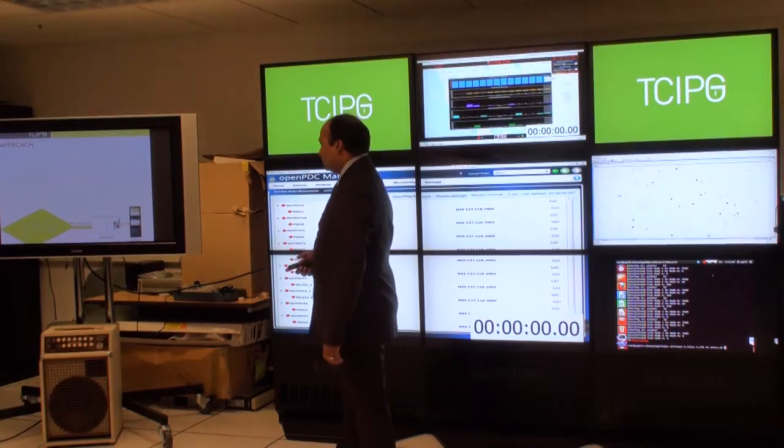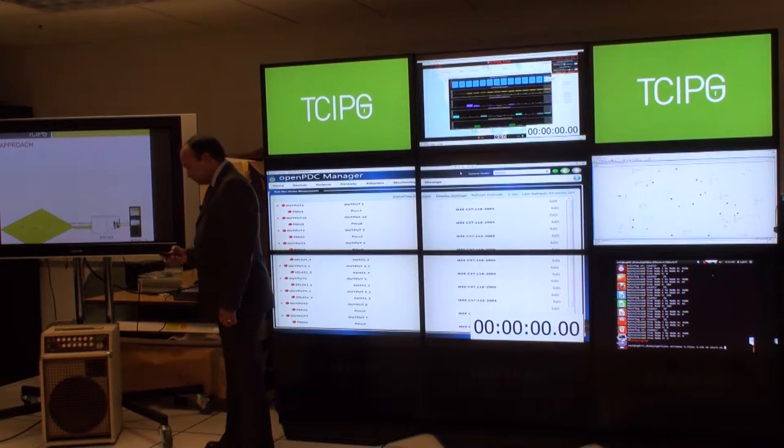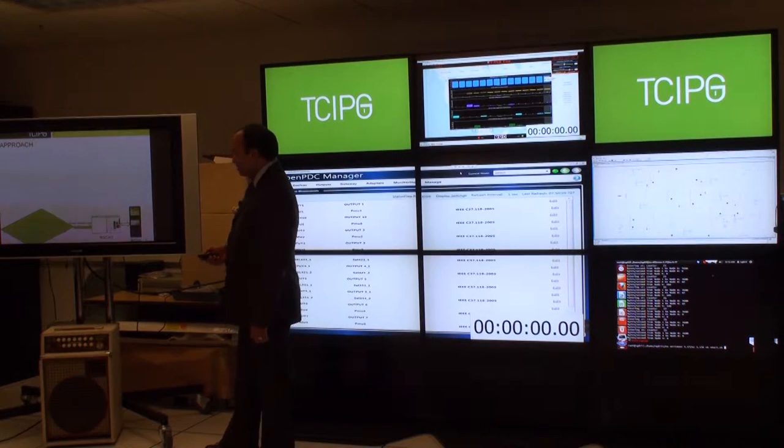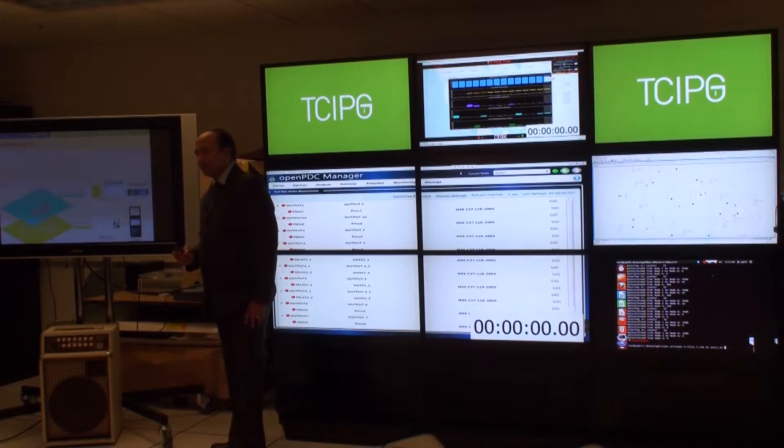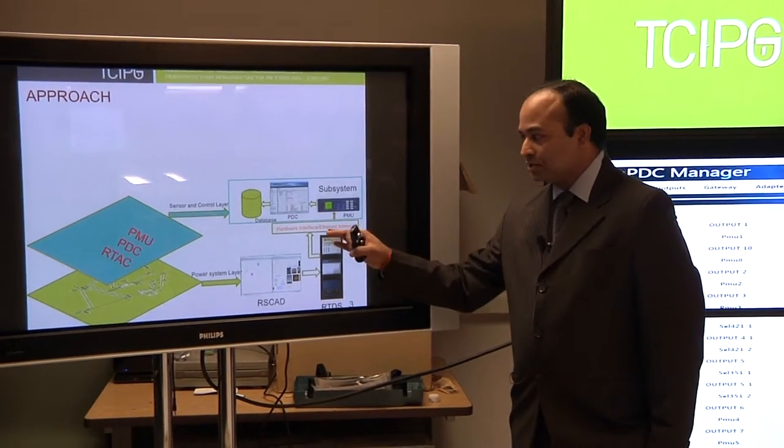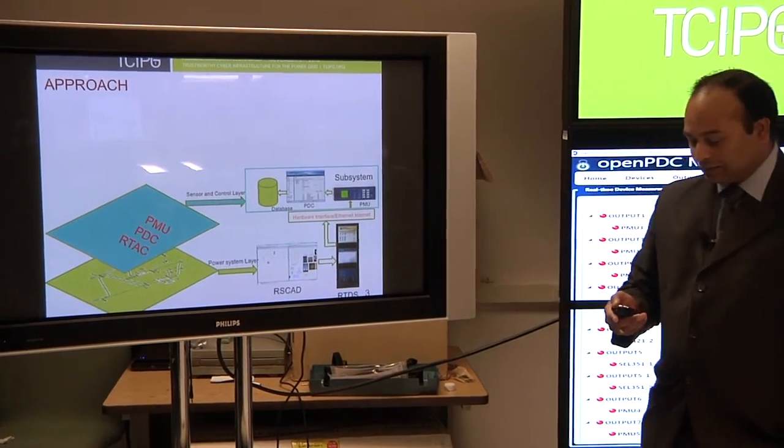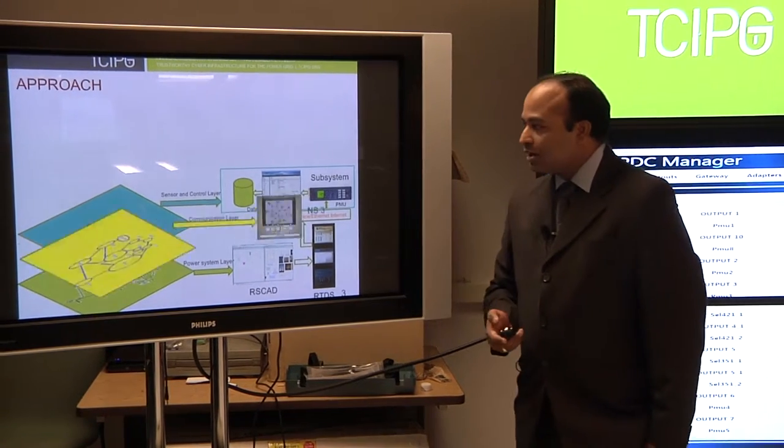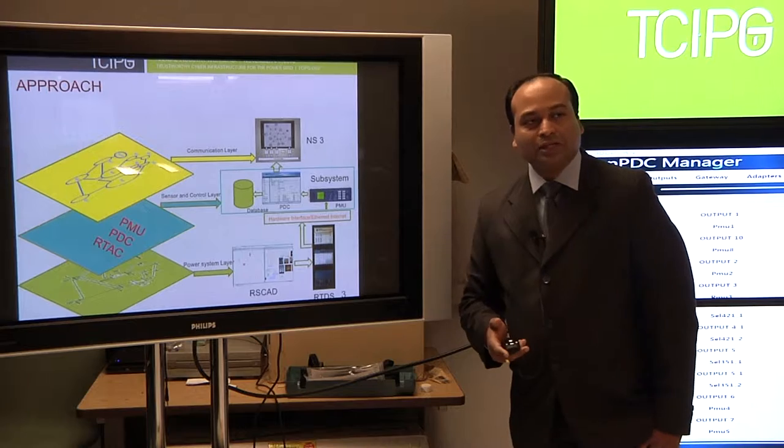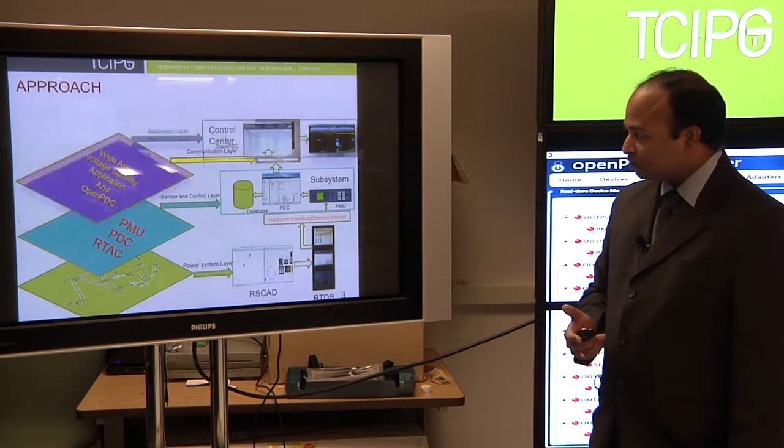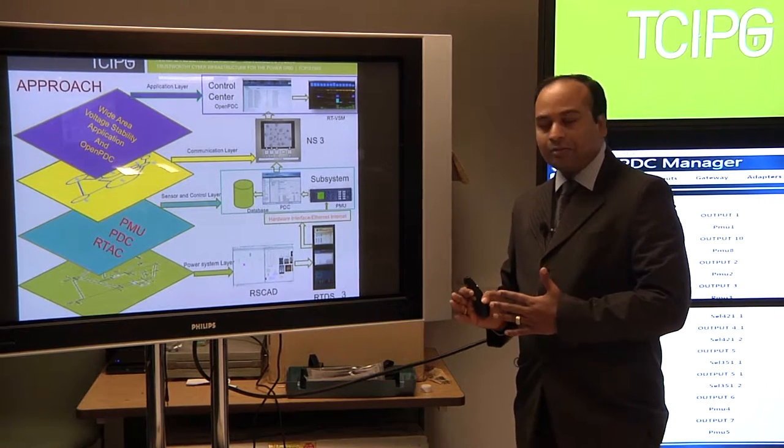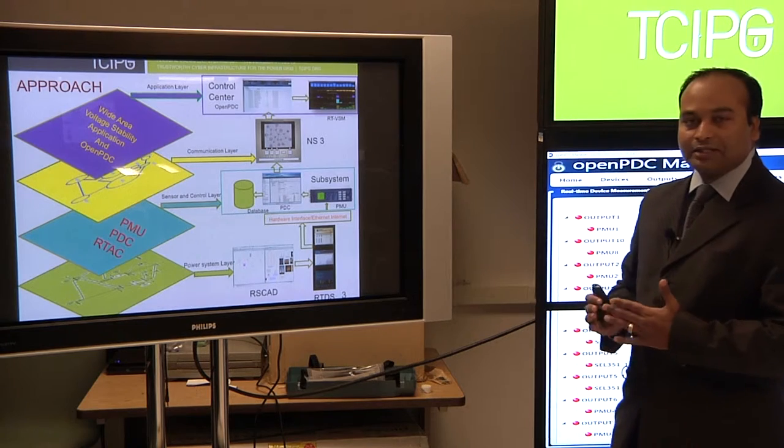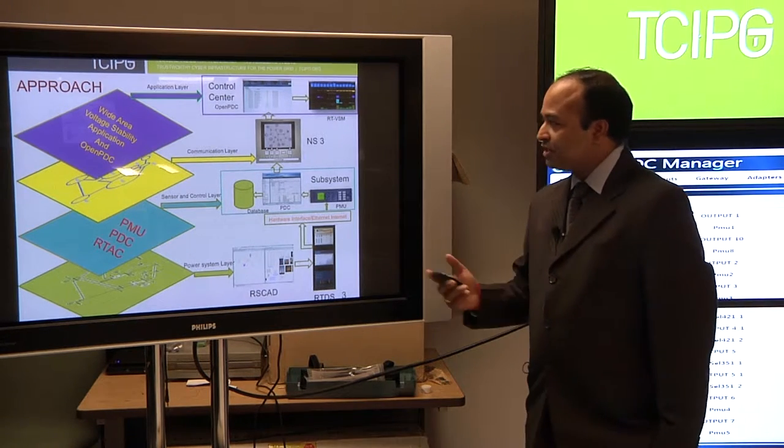Our approach to accomplish this is basically model all the layers of cyber power system. What you see here is a power system layer that's being modeled in RTDS using a real time digital simulator. The second layer is the sensor layer and controller layer at the substation, including the phasor measurement unit and PDC and automation controller. The third layer is our communication layer, which is network model in network simulator 3. And on top of that, we have application layer. In our demo today, the specific application is voltage stability based on synchrophasor data.